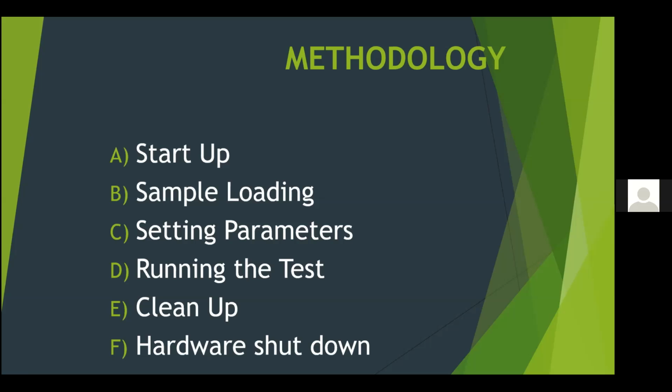And then the nitrogen gas tank was turned on, which would be held at 20 psi, and the sample purge flow should be 50 milliliters per minute. And next is sample loading.